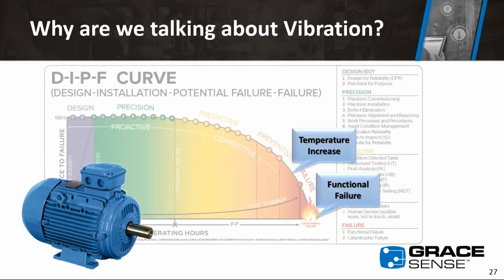Before that, we would typically see a temperature increase. Before the functional failure, there is an increase in temperature due to, if it's a misalignment at the coupling, you would have that, or bearing issues would cause the bearing to overheat and then break down the grease in there. But even before the temperature increase, we'd see a current draw increase on that motor. So we can monitor the current of the motor, and if you start to see it trend upward, you would know that there's some kind of binding or inefficiency in the process making this motor work harder than it did before.